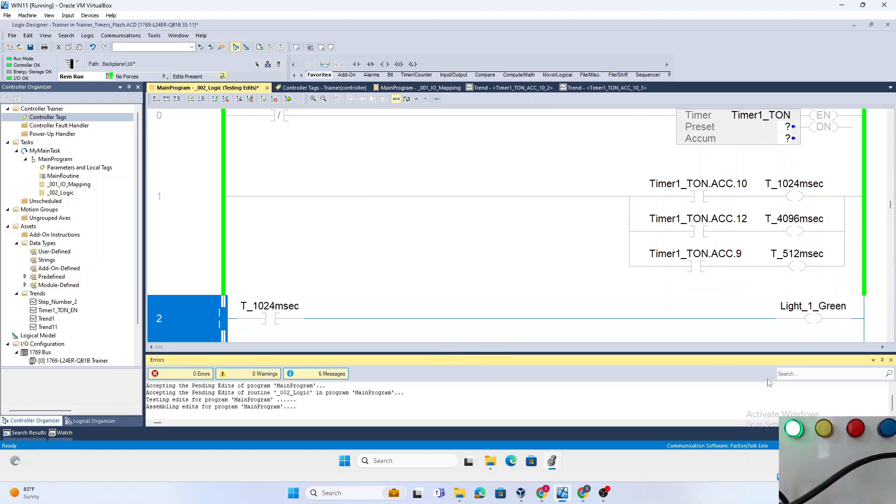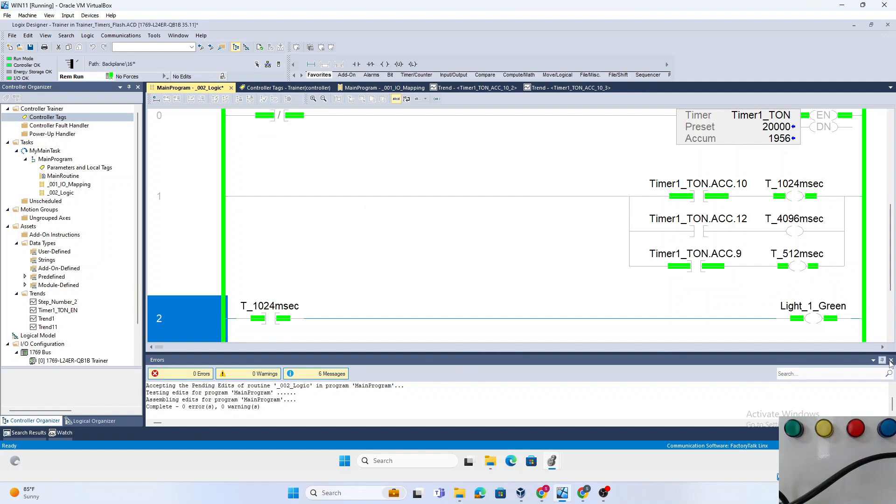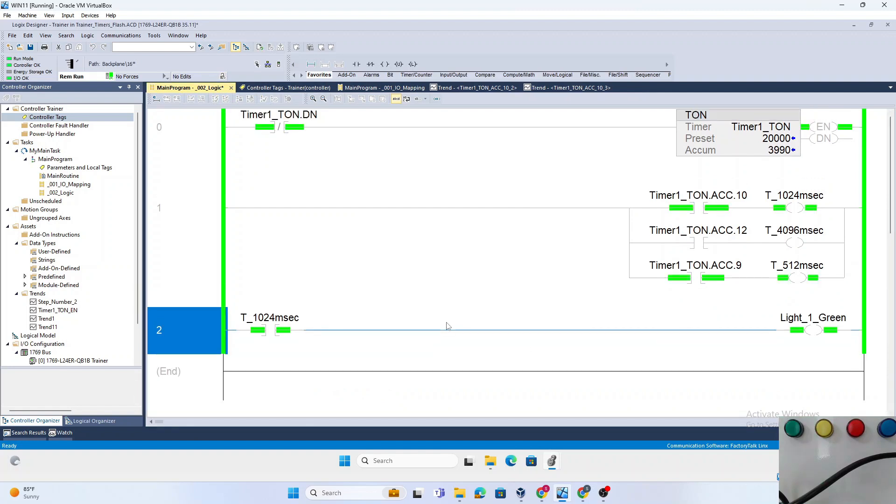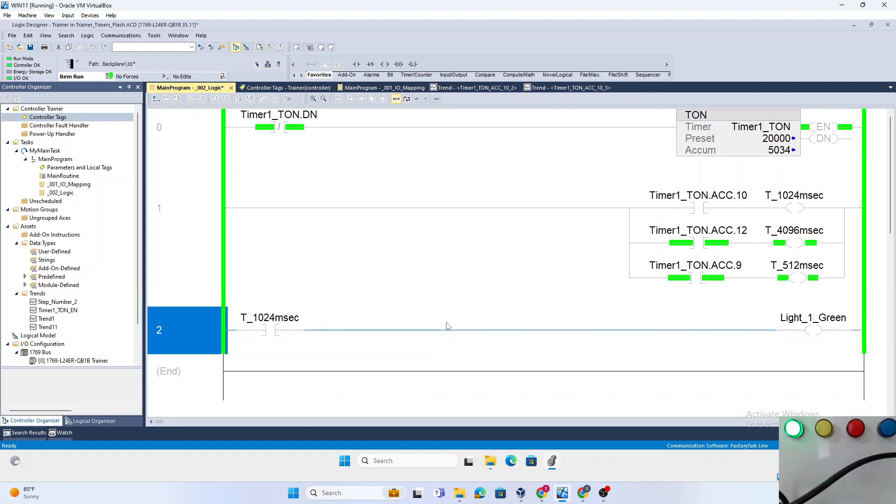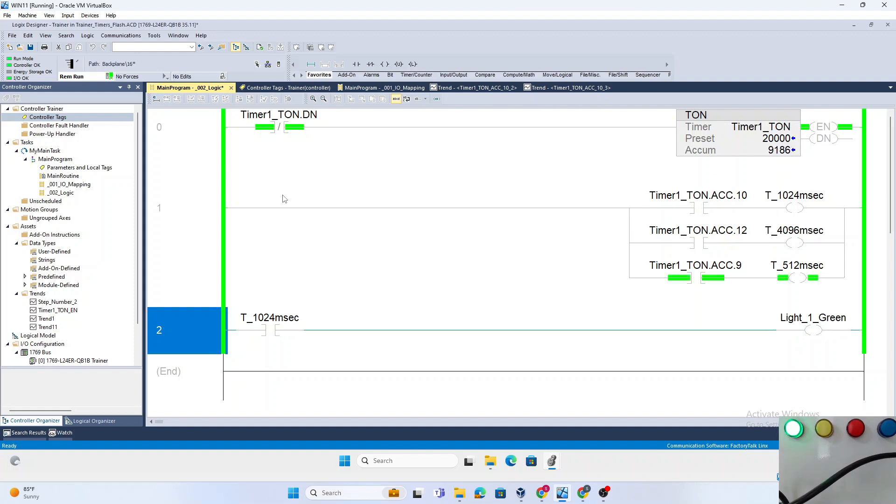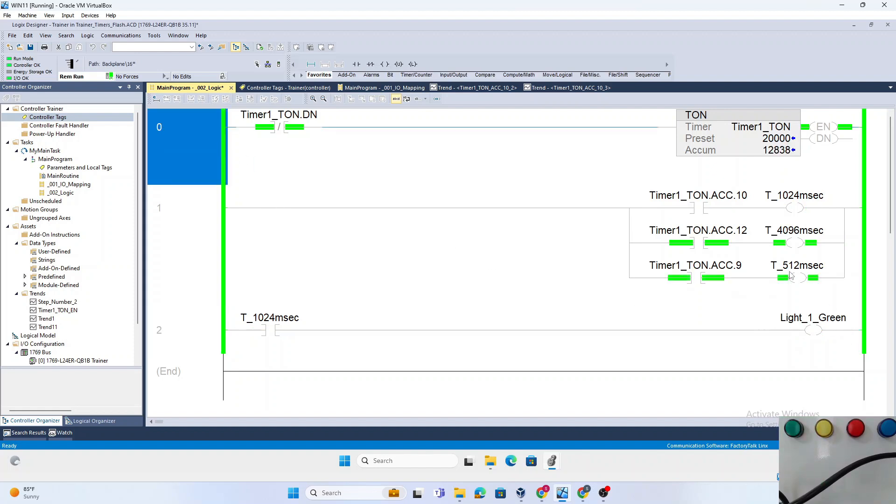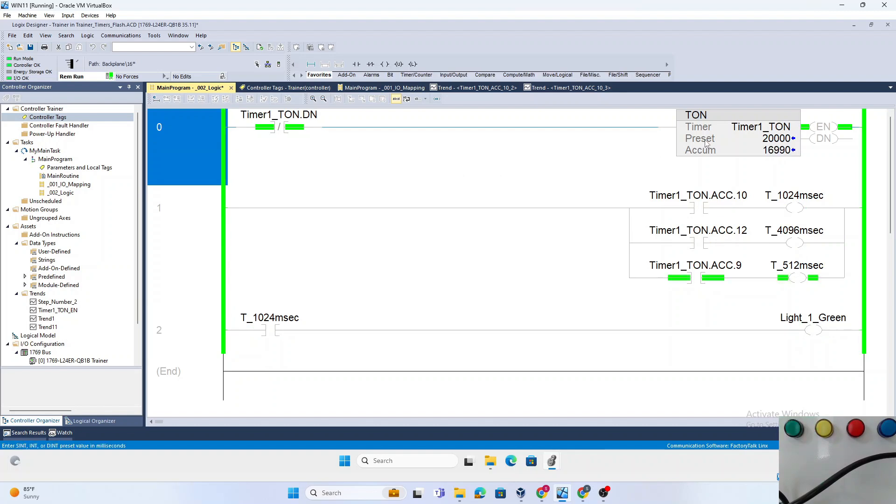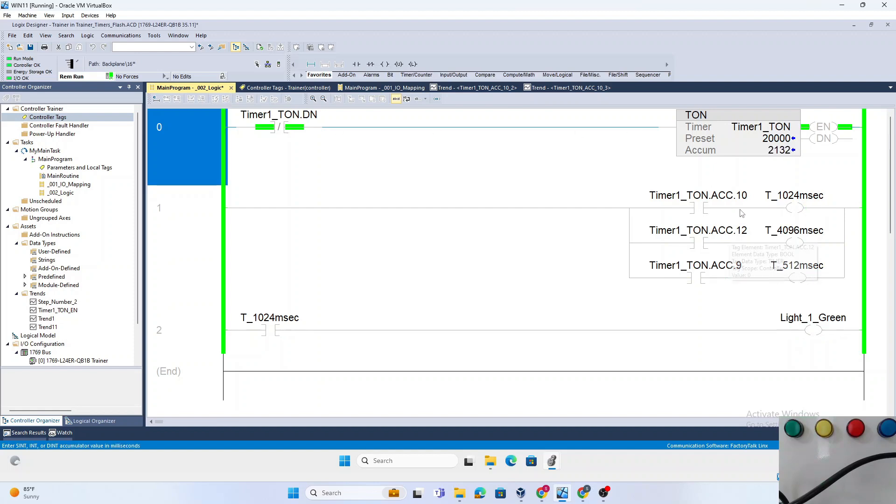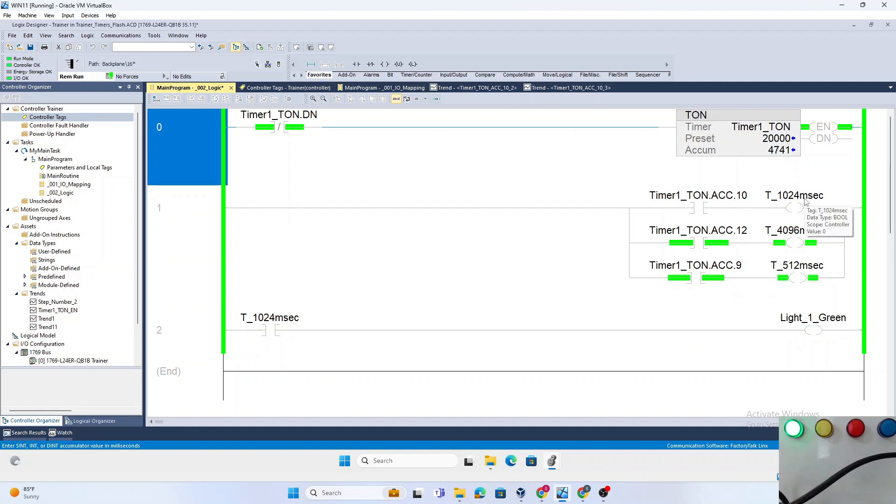So that's how you create a flasher signal. I'll put it back to the 1024. This is one way of using the accumulator bit to make a flasher. In subsequent videos we'll talk about how to create an AOI out of this, but for simplicity's sake, we created a flasher signal for 1024 milliseconds using a self-timing timer and the accumulator dot 10 bit, mapped to a 1024 millisecond bit, and used that to create a flashing signal.